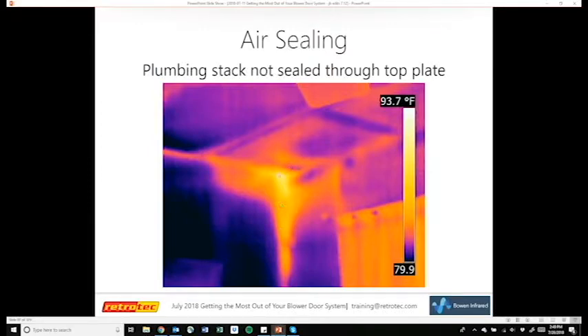Sam showed us a picture earlier of a plumbing stack that wasn't sealed through the top plate. And here we have airflow down along that stack through the unsealed area, and the pressure of the door is creating this airflow pattern that reaches down along that stack, and we can definitely pick up those massive types of leaks. Again, this is on the back of the drywall, not on anything inside the building, inside the structure.